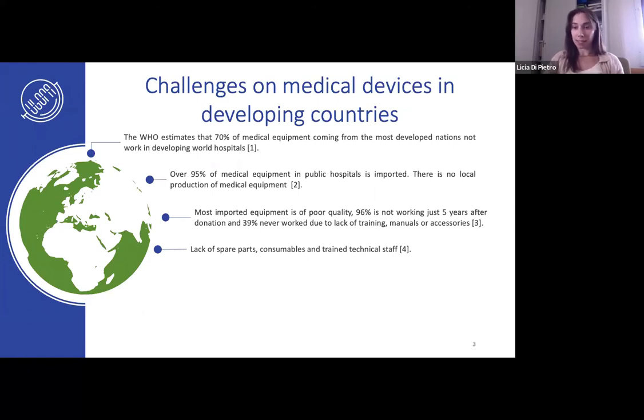The most important design barrier is the lack of spare parts in the target countries. Any device designed for the developing world will be likely to stop working as soon as the first replacement part is required. For example, if a filter needs to be replaced every 6 months, then the device will likely only last for 6 months when placed in a developing world hospital.